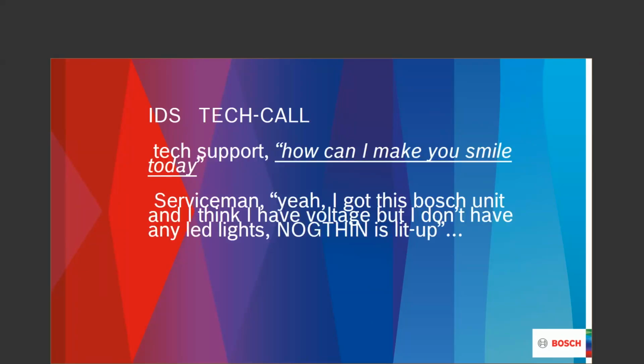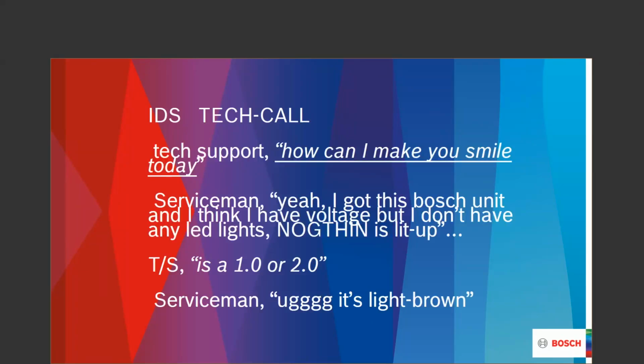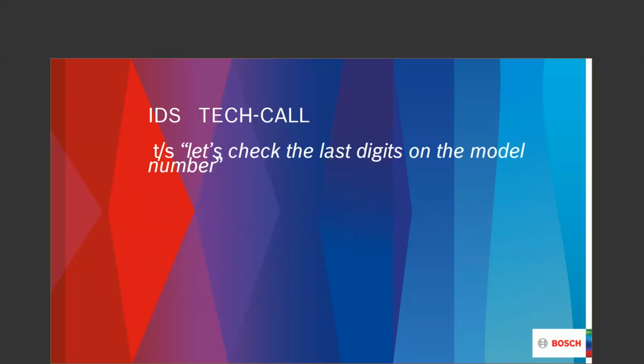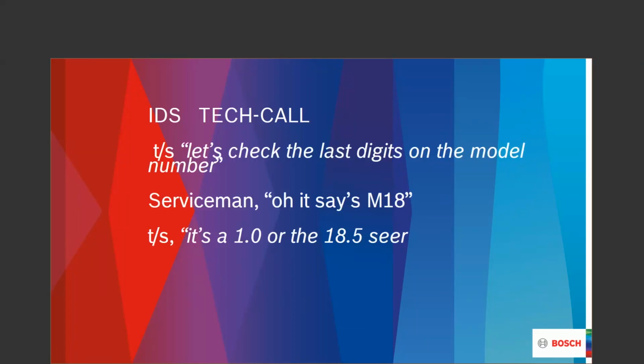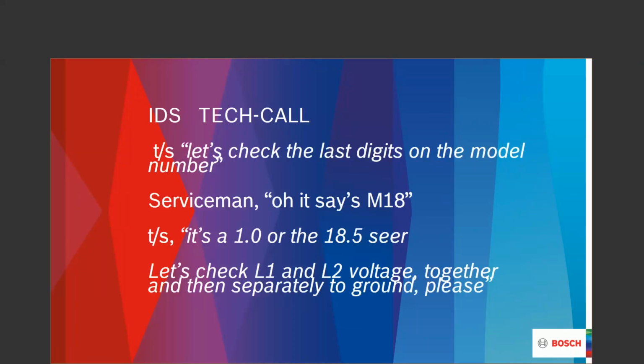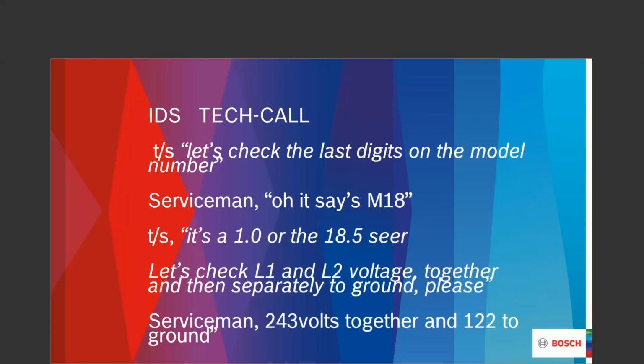Serviceman: Yeah. Hey, I got this Bosch unit, and I think I have voltage, but I don't have any LED lights. Those little things down there are not lit up. Nothing is lit up. Tech support: Is it a 1.0 or 2.0? Serviceman: Yeah, it's light brown. Tech support: Let's check the last digits of the model number. Serviceman: Oh, yeah, it says M18. Tech support: Well, that's the 1.0, or what we would call the 18.5 SEER-rated system. Let's check L1 and L2 voltage together, and then let's check them separately to ground, please. Serviceman: Hey, I've got 243 volts together, and L1 to ground and L2 to ground is 122 apiece.